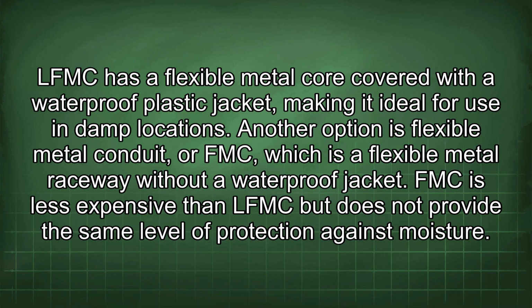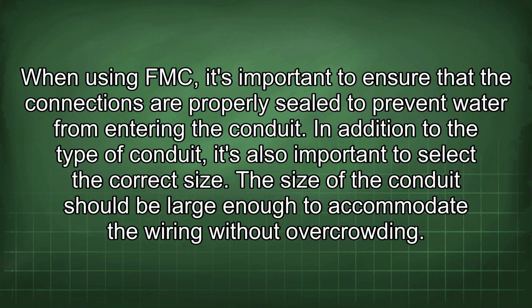Another option is flexible metal conduit, or FMC, which is a flexible metal raceway without a waterproof jacket. FMC is less expensive than LFMC but does not provide the same level of protection against moisture. When using FMC, it's important to ensure that the connections are properly sealed to prevent water from entering the conduit.